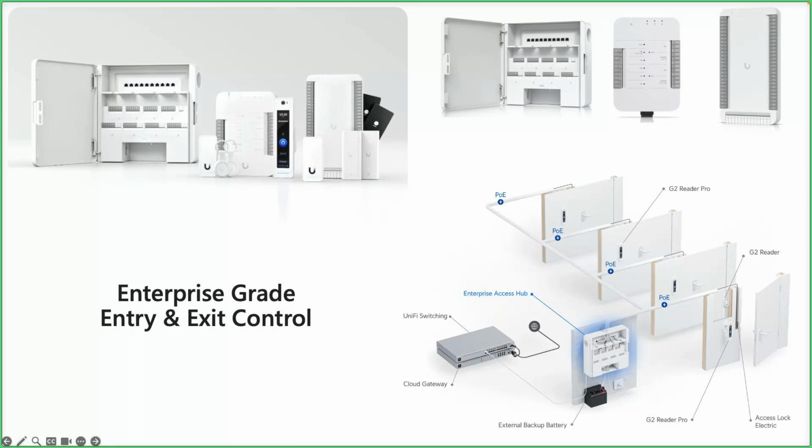And these devices are the primary devices for interfacing with doors, alarms, push buttons, motion sensors, door position sensors, wet and dry contacts. That is the primary brains behind controlling the different doors and interfacing with legacy systems. It can even connect to external sirens or automatic door openers as well if wanted.